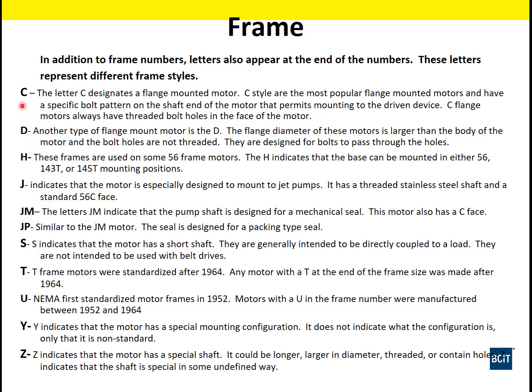The ones we commonly see are T's and U's. U's are an old code, and T's are what most new motors are. Most new motors have a T code on them, or there is no letter code there on a lot of the T frame types. U's are some older motors; you may run into those. Another one I'll point out here is the C letter code. As I mentioned at the very beginning of AC machines, that means a pump or some piece of equipment can be mounted directly onto the motor, and the motor can be the actual support for it. That's what the C codes mean.